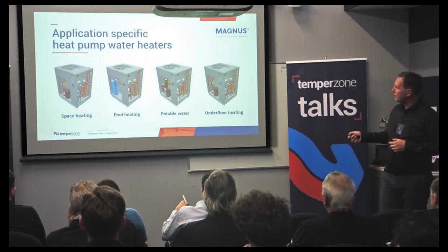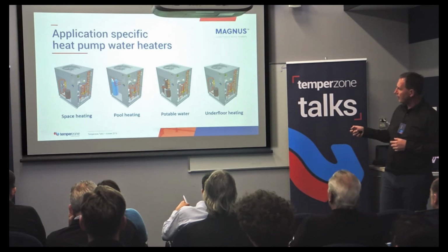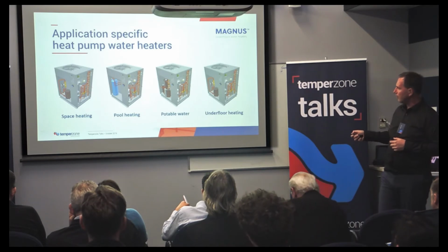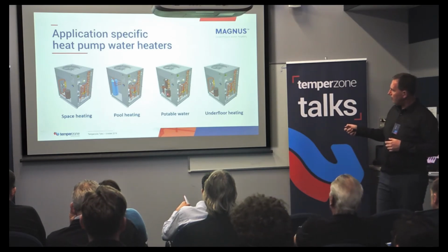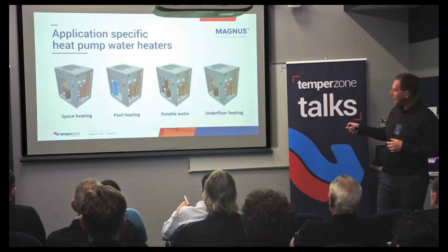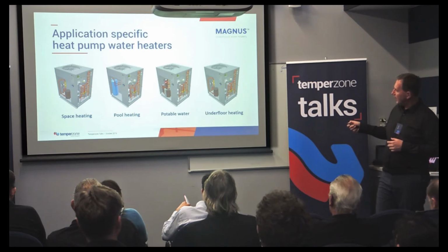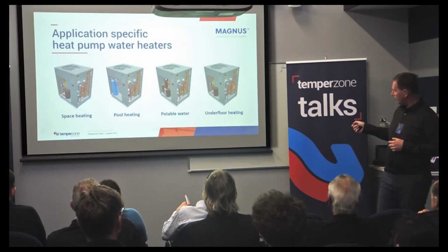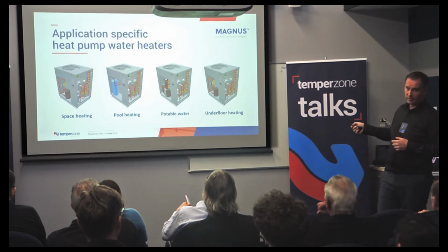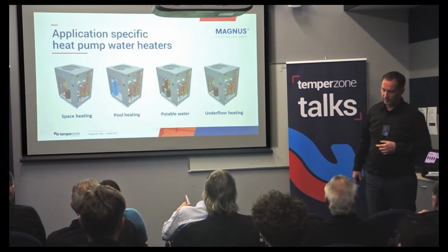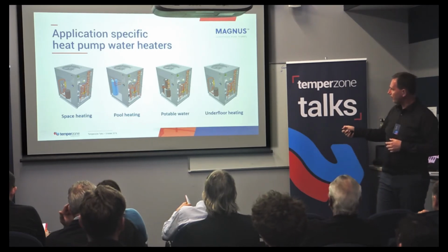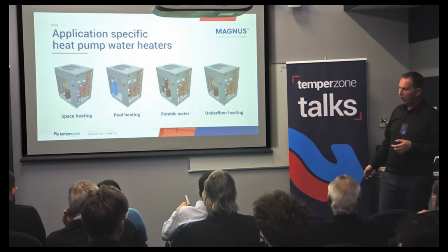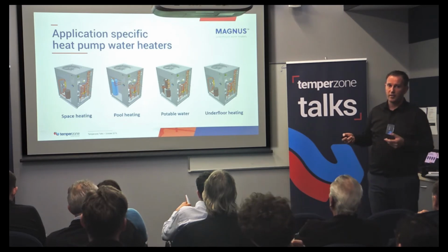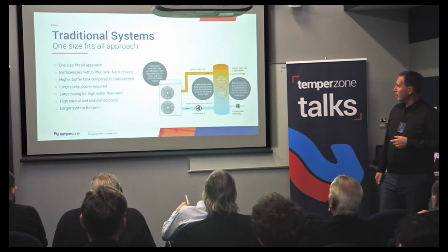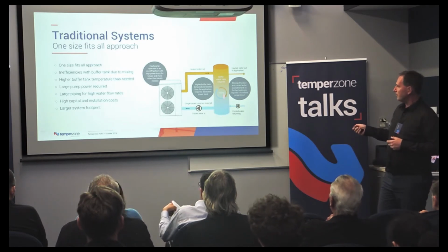So we've come up with different configurations of each unit. This is the titanium heat exchanger for doing DX into pools. The potable water has a de-superheater. This is the vapor injection. This is the superheater to get the high temperature, and then your underfloor system. This is what you saw downstairs, and then there's another 5 variations of this, where we can have part of this, and one of these spots reverse cycle, and all the rest of it. A lot of the units come with turnkey controls. So this is what the industry is largely doing now.